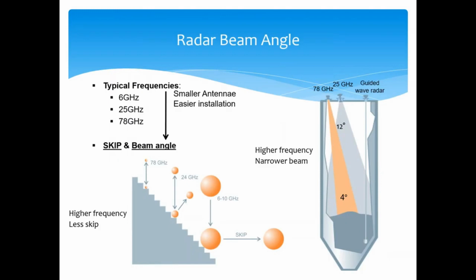Wanted to talk about this. This is a really good way for me to visualize what the beam angle really means for you. Let's look at one of these tanks that might be a very tall silo with some sort of solid material in it. It might be 80 or 100 feet tall and only 10 or 12 feet in diameter. As Sean mentioned on some of the questions you've asked, if I've got a radar up there with a 12-degree beam angle, one of those medium frequencies, we're not going to make it all the way down to the solids level before we're reflecting off the sidewall.